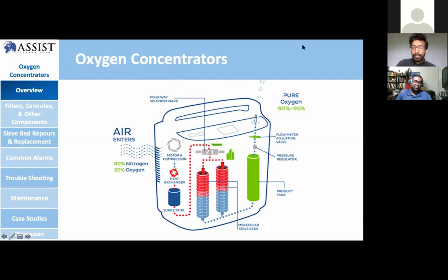So we're going to talk about the oxygen concentrator, like what Benjamin said earlier. We did speak about the oxygen concentrator, but this time we're going to dig much deeper into the details. Everyone knows how an oxygen concentrator works as a biomed. Normal air contains 80% nitrogen and 21% oxygen, or 20% oxygen, that is pushed into the motor, compressed, and goes through the heat exchange and to the surge tank and ends up in the sieve tank or zeolite tank, which absorbs the nitrogen and releases the oxygen from the sieve tank to the product tank.